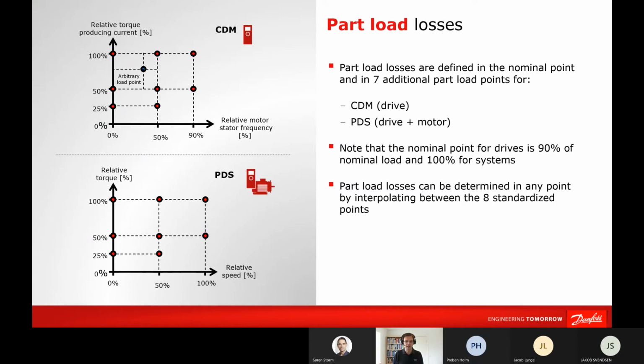And the standard defines 8 part load loss points, and if you take and define these points, then you can calculate an arbitrary load point by interpolating between the 4 neighboring points. It is also possible to extrapolate.